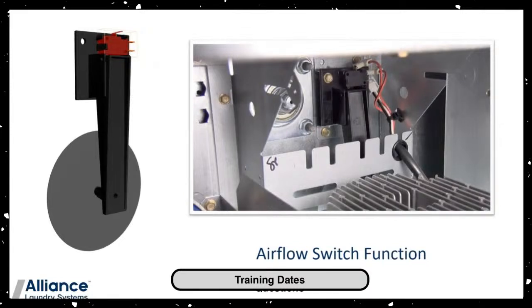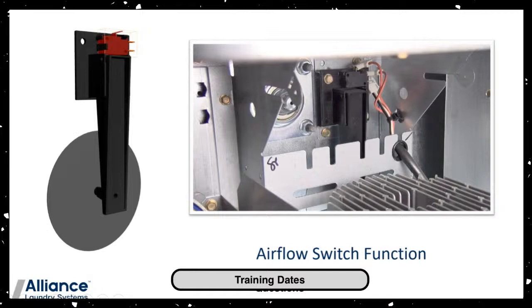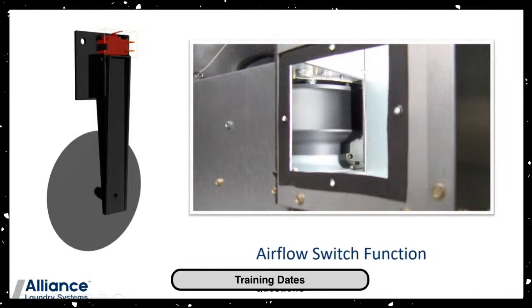Looking at it on the left, the top part highlighted in red is the actual microswitch, the switch that's either closed when the damper is drawn shut or open when the fan stops and the damper is just hanging. This little video clip on the right shows it being drawn shut right now when the fan starts, and then when the fan stops, gravity pulls it back. So we're verifying that we have airflow. If we don't have airflow, we don't want the heater to turn on. We have to have proper airflow, and the controls now do a very good job of monitoring this airflow switch and its function to prove that it's working properly. If not, we will have issues. So we'll talk about that.